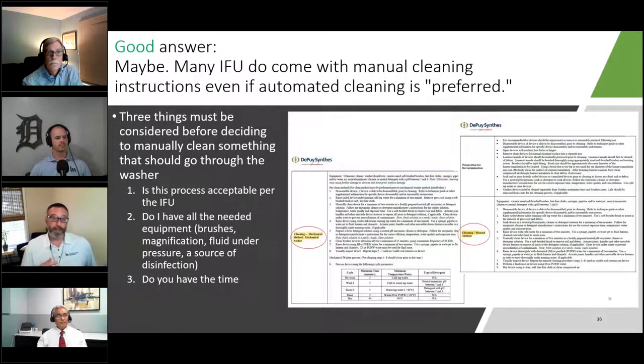If you don't see both manual and automated instructions, you may not have a choice. We say to follow the IFU, and if it says mechanical or automated cleaning and nothing else, then just assuming that scrubbing it in your hand wash sink works is a bad assumption. So if you're going to do this, here are the things I want you to consider.